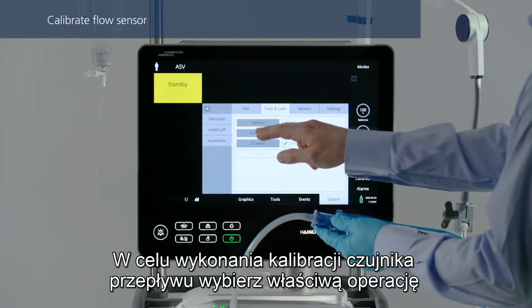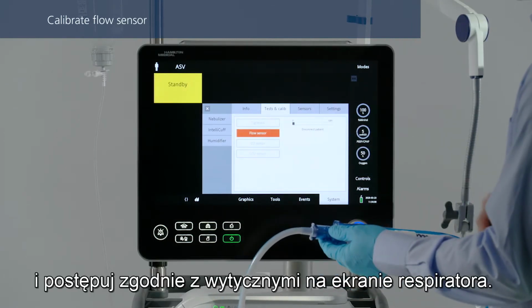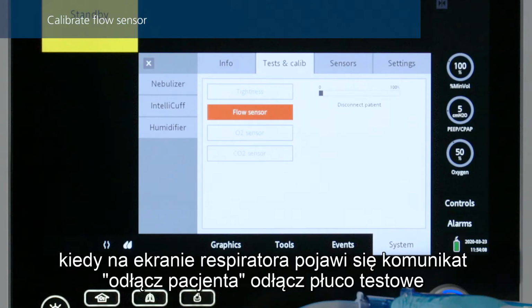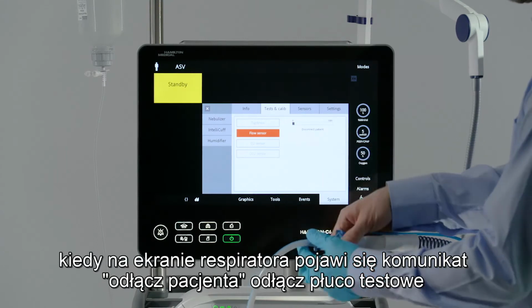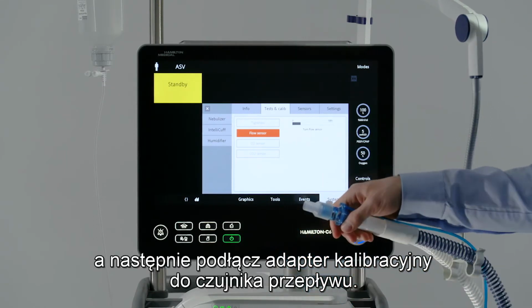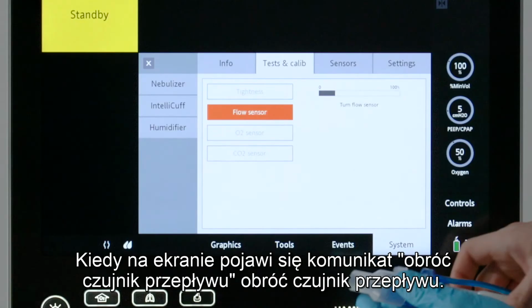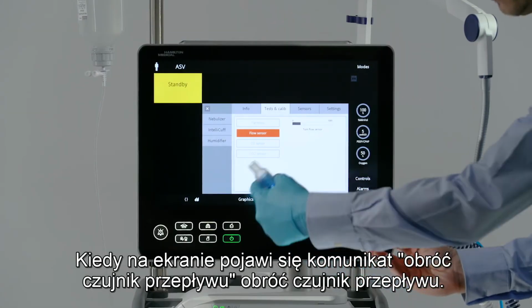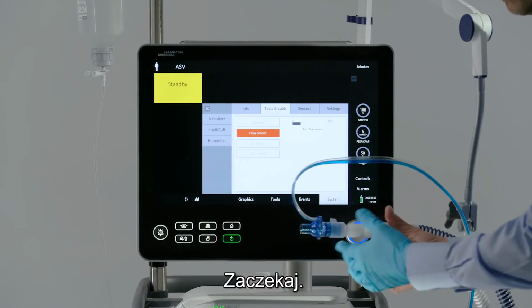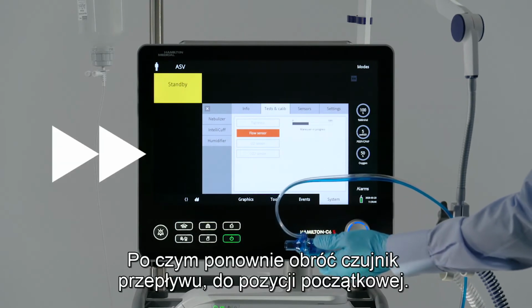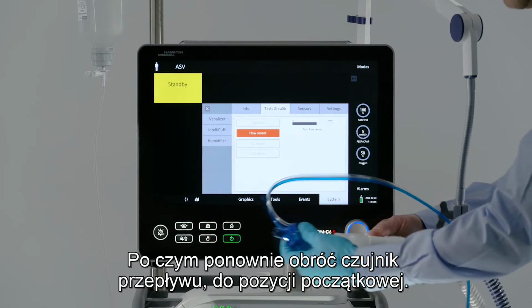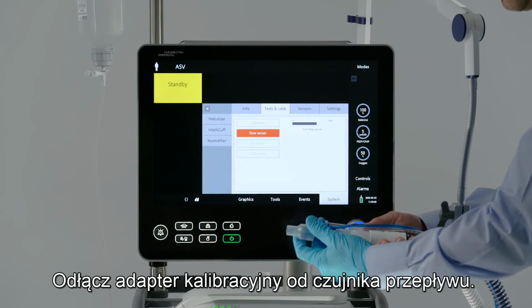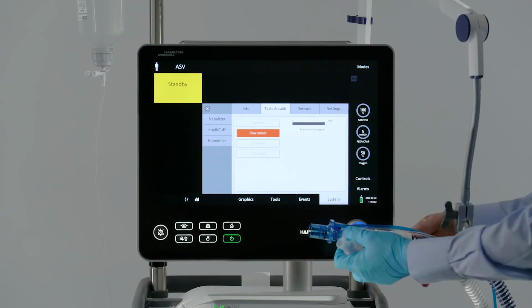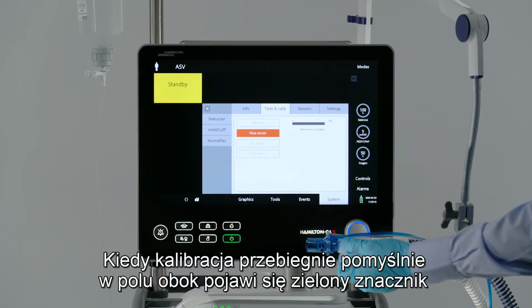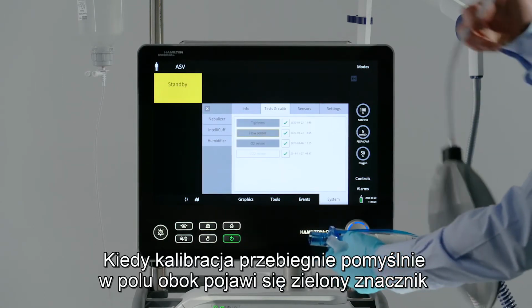To calibrate the flow sensor, select the desired operation, then follow the instructions from the ventilator. When the disconnect patient message appears, disconnect the test lung and attach the adapter to the flow sensor. When the message turn the flow sensor appears, flip the flow sensor. Wait. And then, flip the flow sensor back to its starting position. Disconnect the adapter from the flow sensor. When calibration has been completed successfully, a green check mark will appear.